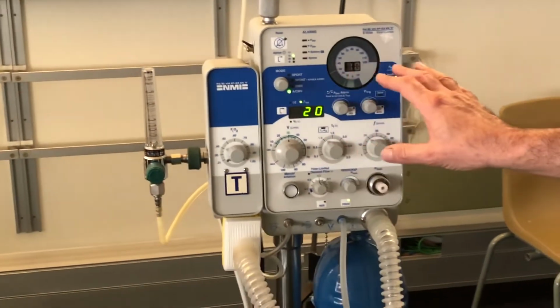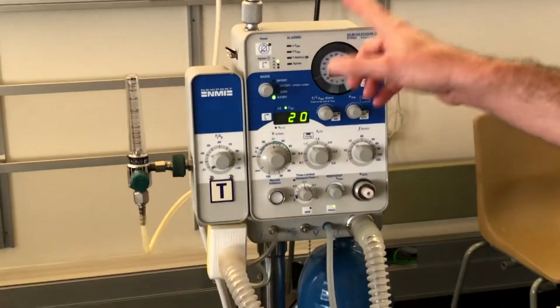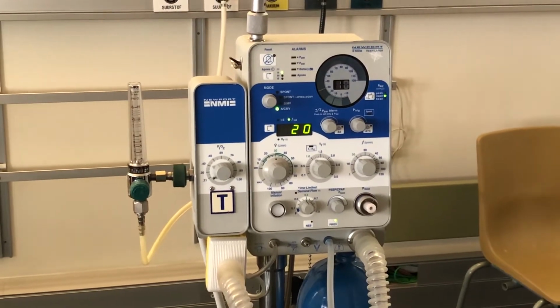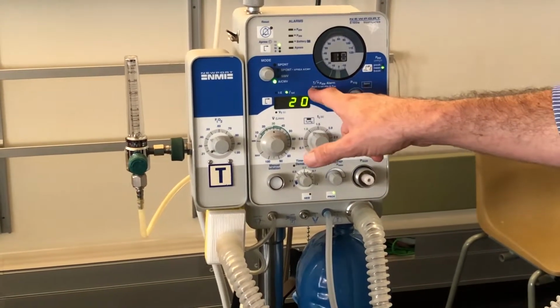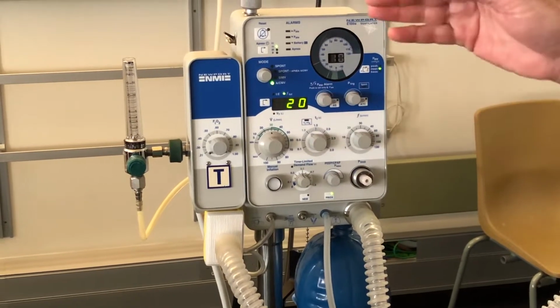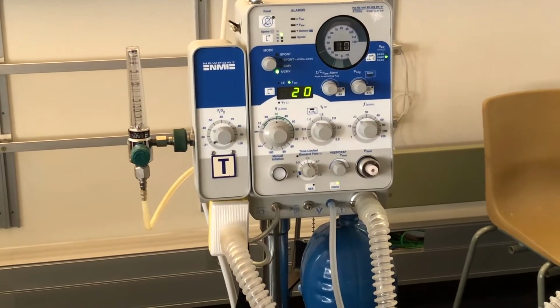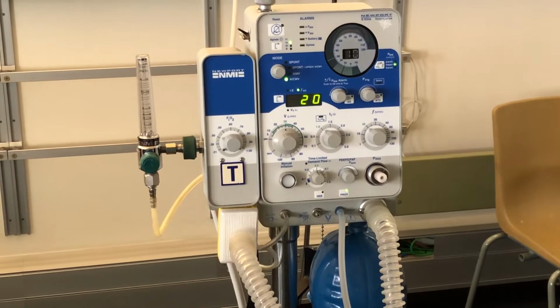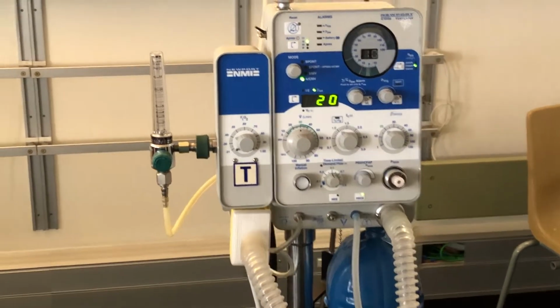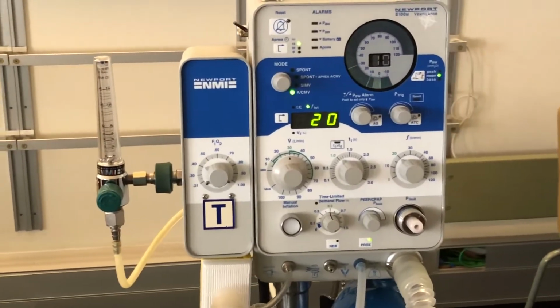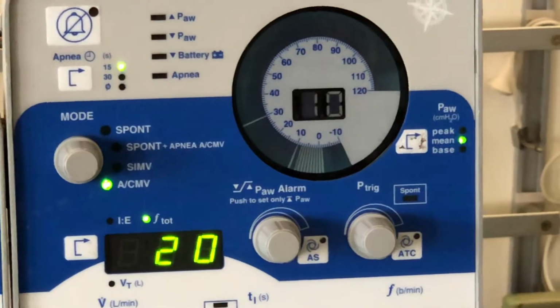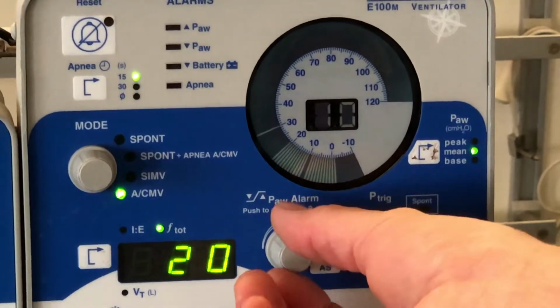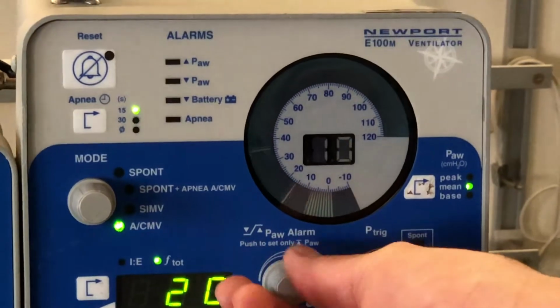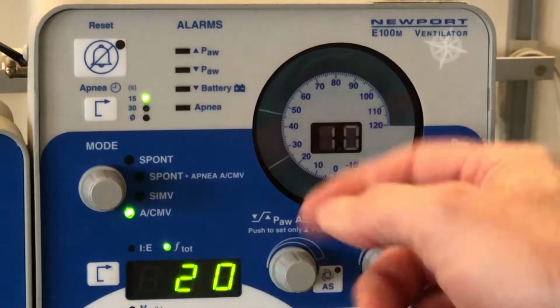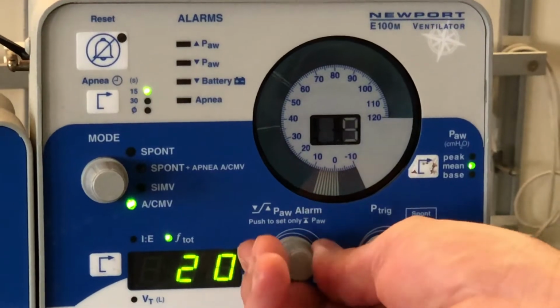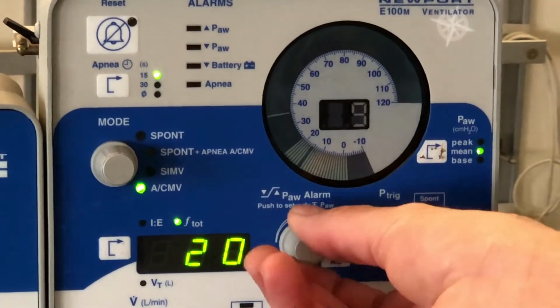Once we've got those settings taken care of, we need to set up the alarms on the machine. So if we look at the first alarm setting we have here, it's for the upper and lower airway pressure alarm. The upper pressure alarm is a limit to prevent patient injury, and the lower pressure alarm is to detect disconnects from the ventilator. And we can move the alarm settings by turning the dial, and you'll see there the upper and lower pressure limits scrolling around as I turn the dial.